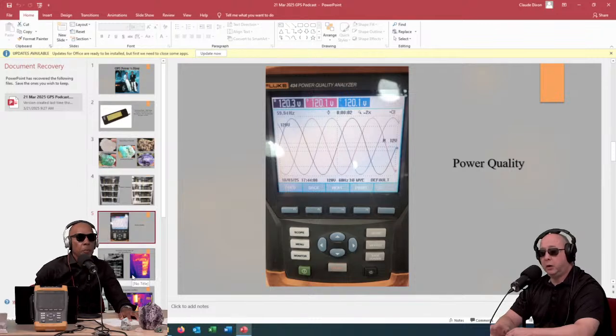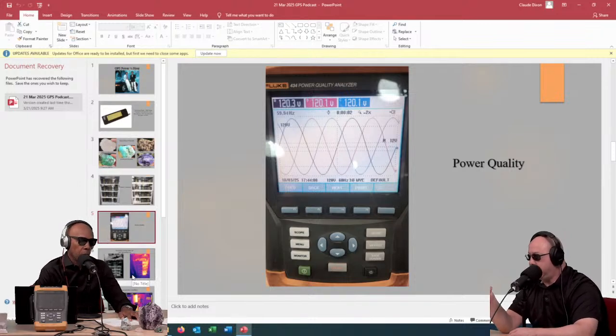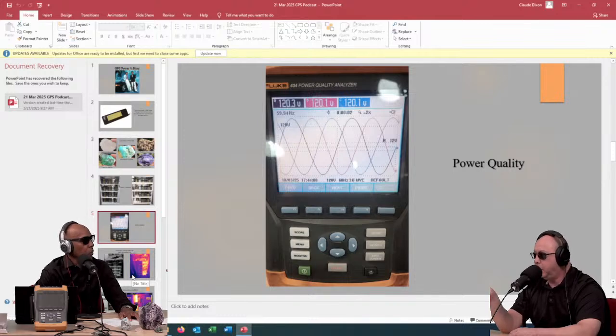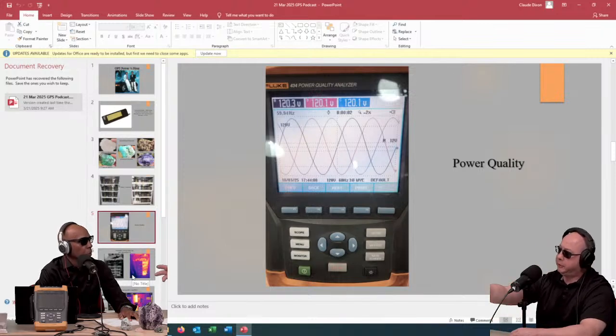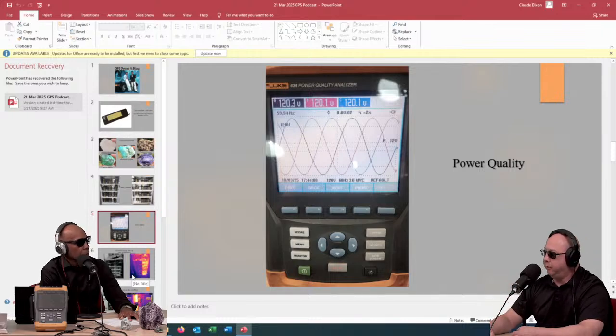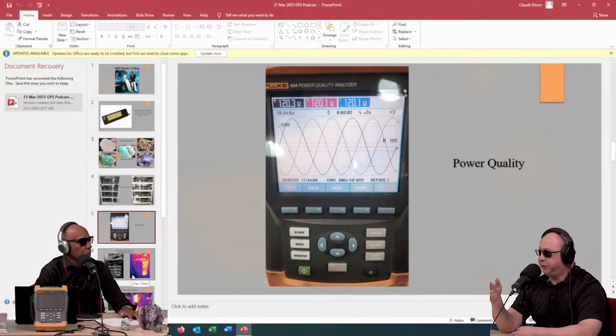With the clamps we're actually measuring amperage, and then there's an alligator clip that clips onto the terminals for the voltage. The clamps do the amperage coming out from the unit. So we can measure the voltage, the amperage, and also the phase rotation at the same time.